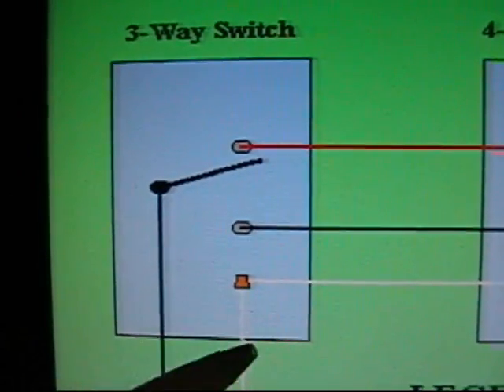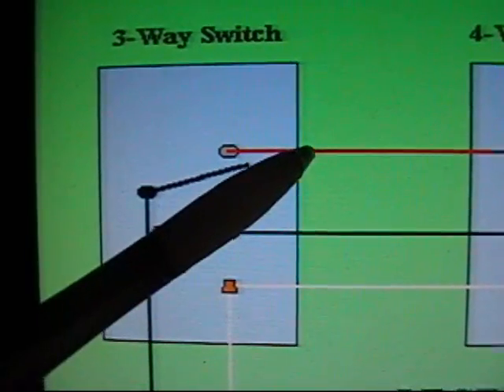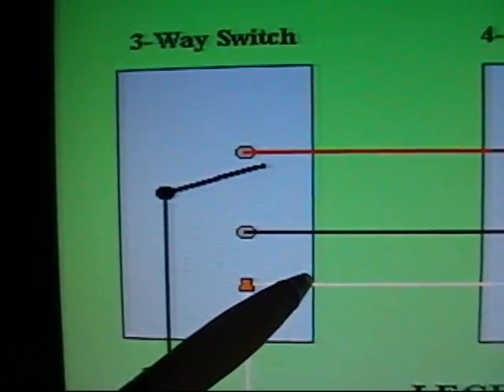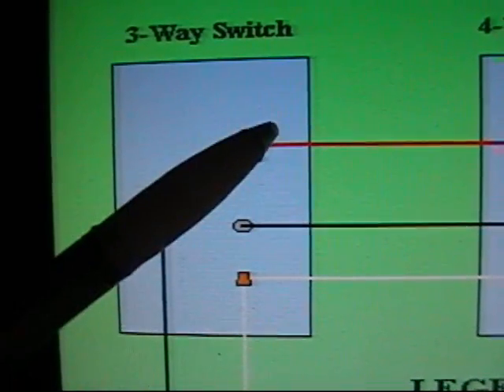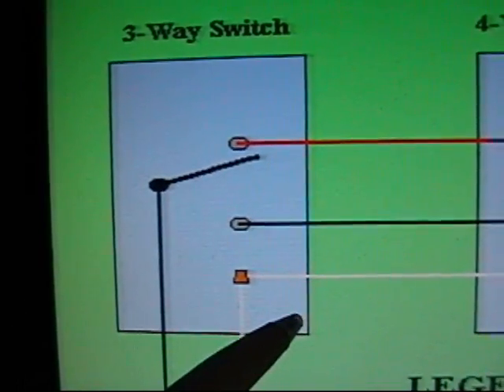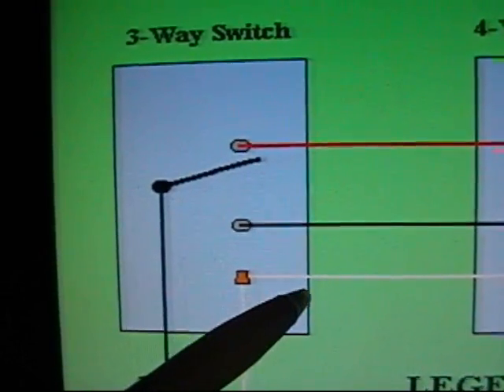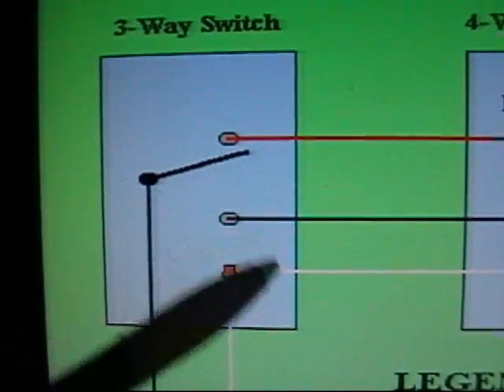So you can, like I say, use 12-3 with ground, but that's pretty expensive. But if you have some heavy-duty lighting, you could probably do that. But most cases you use 14-gauge wire. Going back to the switch drawing again, this is where your black wire would come in from the breaker panel. That's your feed. This would be your travelers. One would go here, one would go here. Doesn't matter whether you use the red or the black, doesn't really matter at all. So that's how you do that.